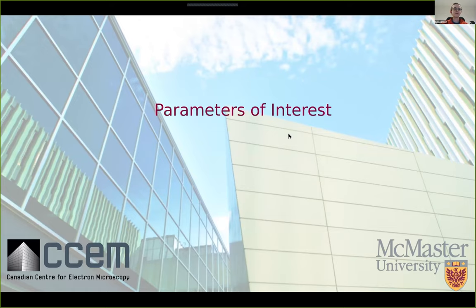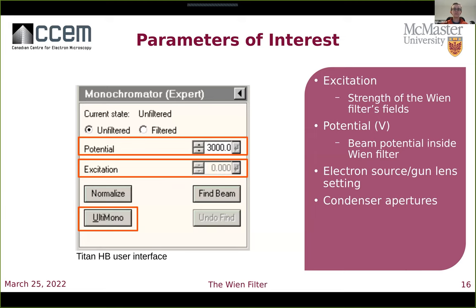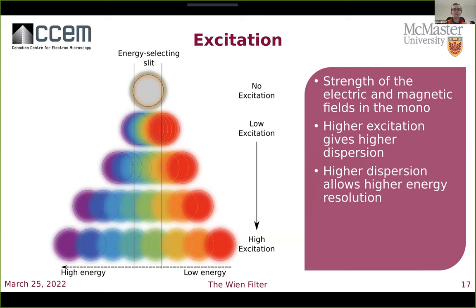The parameters to set up include the excitation, which represents the strength of the Wien filter's fields, and the potential of the monochromator, which determines the energy at which electrons travel through the filter. Other important parameters include the choice of gun lens setting and the selection of condenser apertures. At zero excitation, the beam is not dispersed according to energy — the exit plane holds simply an image of the source. At low excitation, there is only a little dispersion. As the excitation is increased, the beam is dispersed more strongly, and the energy selecting slit — which is a fixed size — can select a smaller range of energies, giving higher energy resolution but less current.